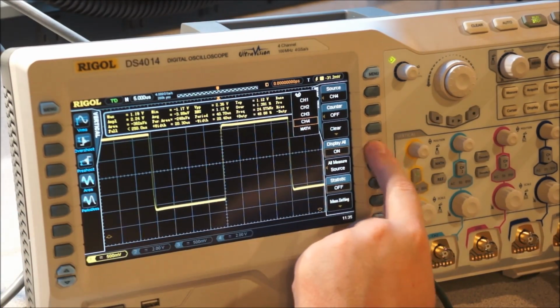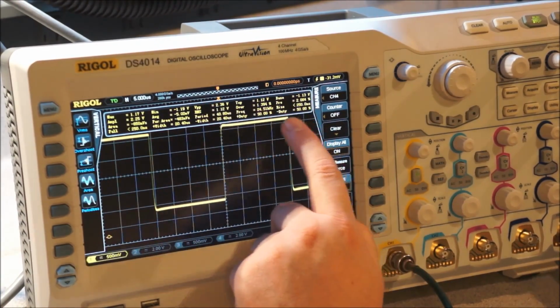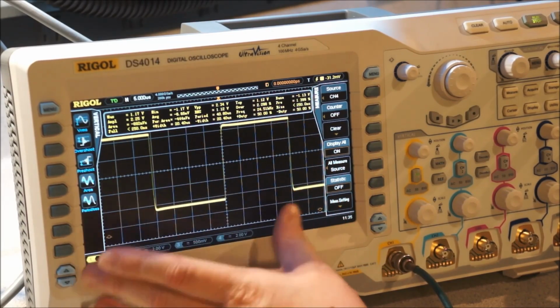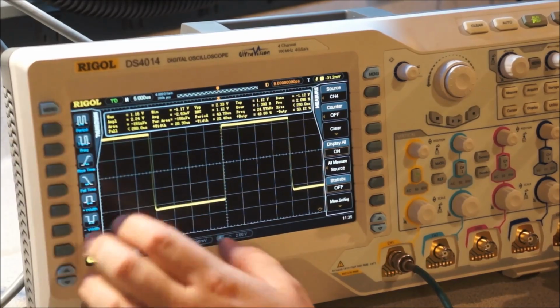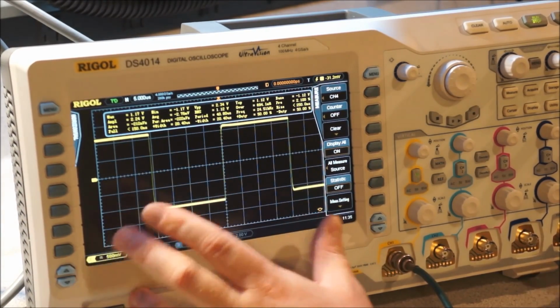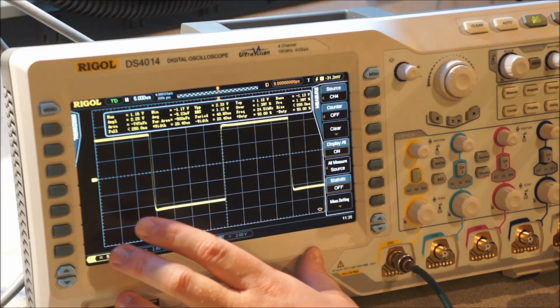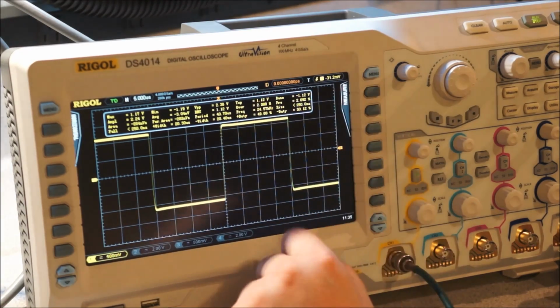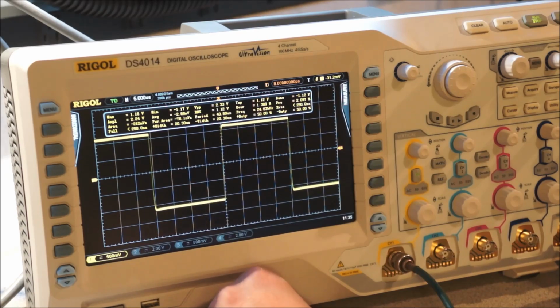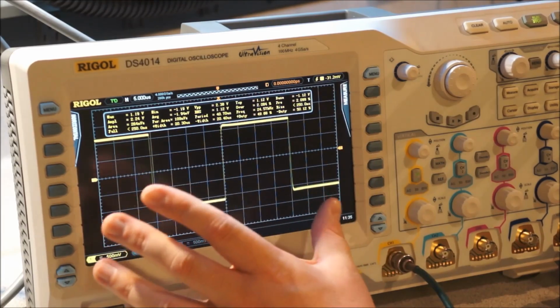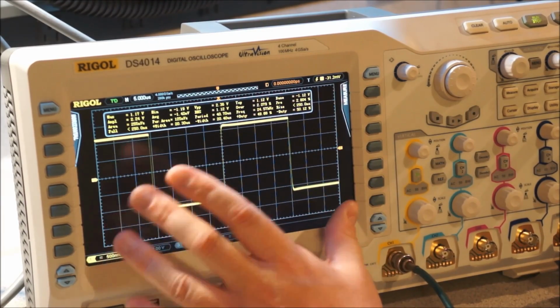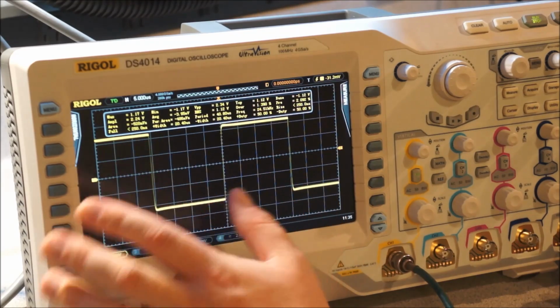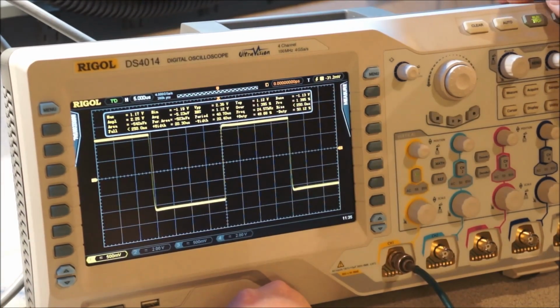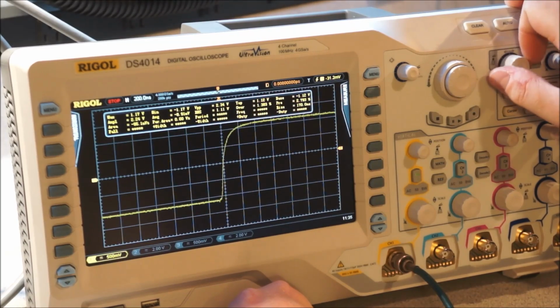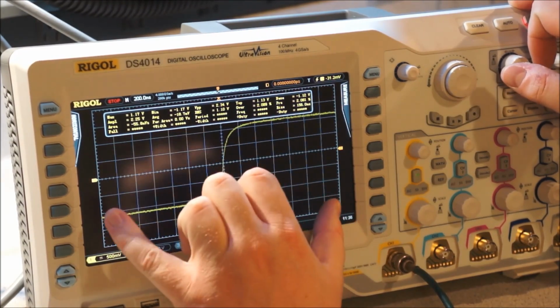But you can see, this is all of the various math they can do on the channel. One of the downsides of the Rigol scopes, and this is also true of the Agilent scopes, but it's not true of the Tektronix scopes, and it's really one of the few reasons the Tektronix scopes have any significant advantages at this point, because the Tektronix scopes have such crap waveforms per second, is that the Tektronix scopes perform the measurements like these on the actual entire width of the sample data. So if you have 8 megapoints of sample data, or whatever their sample size is, it performs the measurement on the entire sample data. Whereas with scopes like this, it only performs it on the data that is displayed.